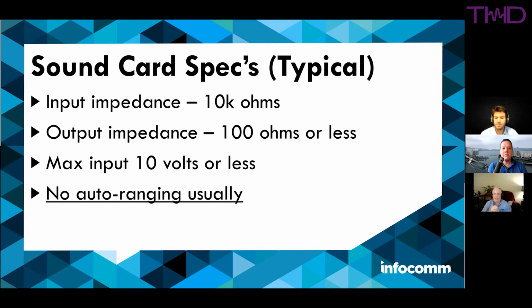So what the auto ranging circuit does - in every AP analyzer, the analog signal hits the auto ranging circuit first. There's a comparator circuit that checks what voltage level you're at. If it's a really low voltage level, it'll kick a bit of gain in, so the signal levels are always, as much as possible, within the sweet spot of that converter.